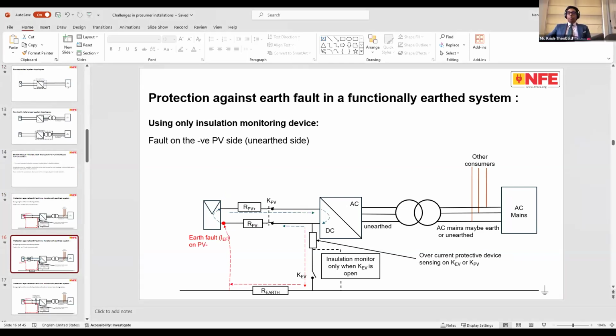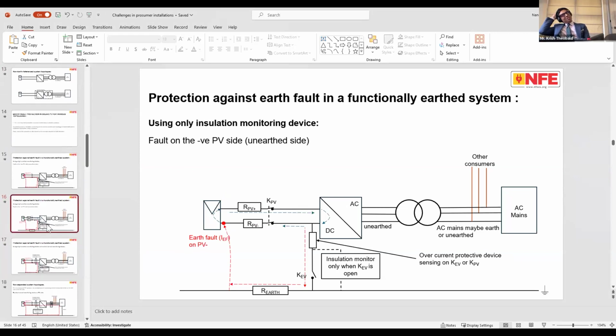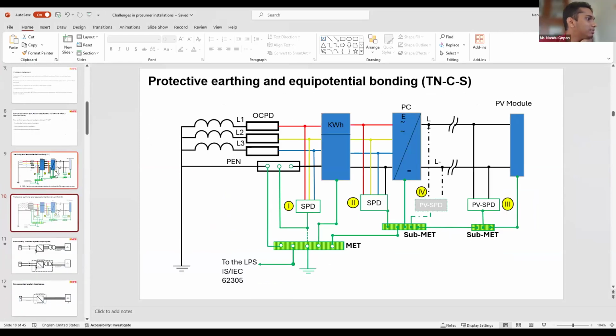Most of the discom engineers demand separate earthing for AC and DC. Is this correct? Please share your inputs. That is what I'll explain here again. It should be connected with equipotential bonding. You are supposed to do it. The earthing on the AC side and the DC side, you are supposed to connect it. That's it.